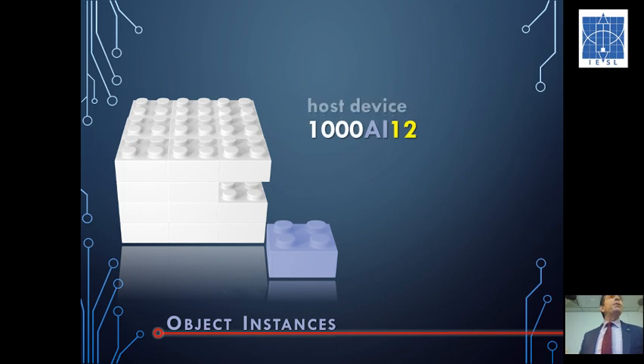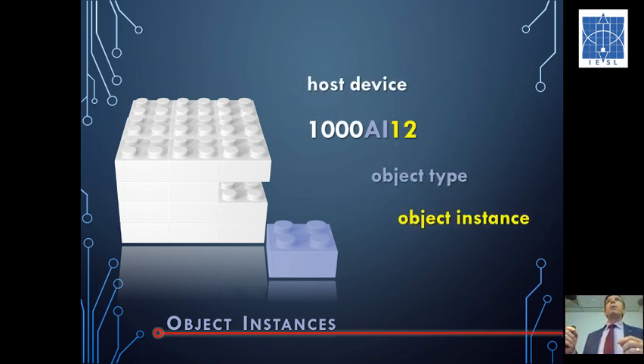So in this particular case, if we go back to our temperature sensor, we spoke about the object living inside the device, and in this particular case, the device is number 1000. The object type is an analog input, and it's the 12th analog input. So that object is 1000 AI12.